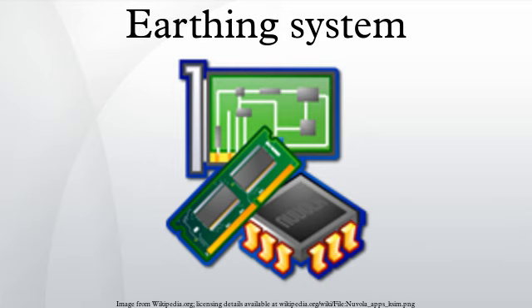Comparison. Other terminologies. While the national wiring regulations for buildings of many countries follow the IEC 60364 terminology, in North America, the term equipment grounding conductor refers to equipment grounds and ground wires on branch circuits, and grounding electrode conductor is used for conductors bonding an earth ground rod to a service panel. Grounded conductor is the system neutral. Australian and New Zealand standards use a modified PME earthing system called multiple earth neutral. The neutral is grounded, earthed, at each consumer service point, thereby effectively bringing the neutral potential difference to zero along the whole length of LV lines.